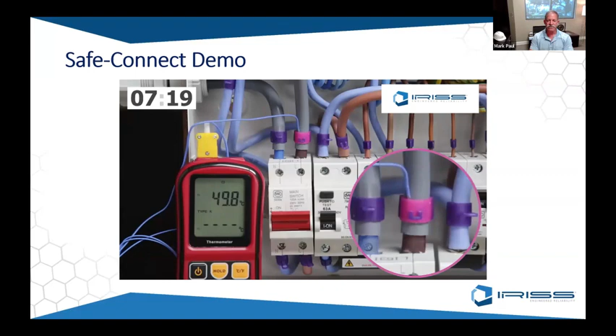Here's a real-world example. We had these thermal clips at a customer site, and they were having problems with their chillers. They did not know what the issue was. We put these on there, and they found exactly where the problem was. They went back in and did a thermography reading, that's the image on the right, and found we've got some really hot conductors here. There's an issue, they traced it back, and we were able to find the problem and actually solve an issue that had been bothering them for a very long time.